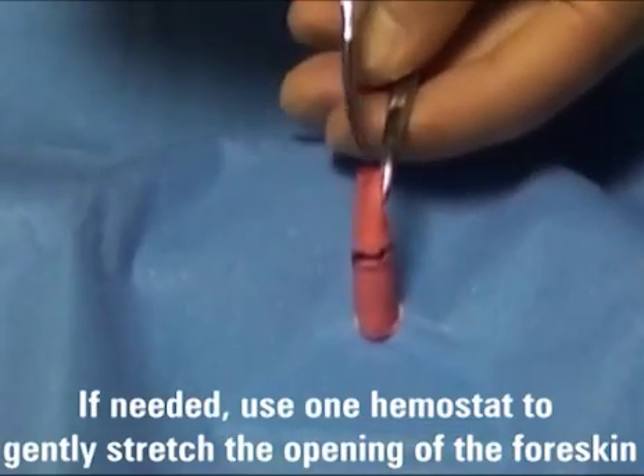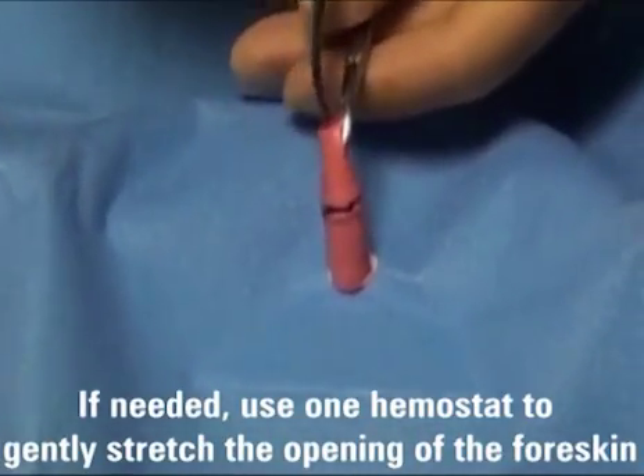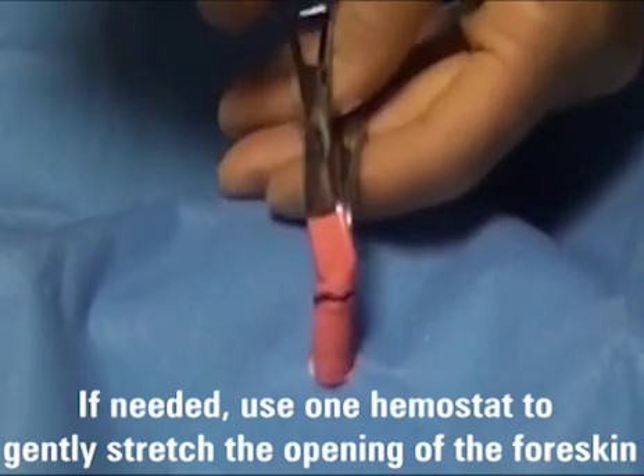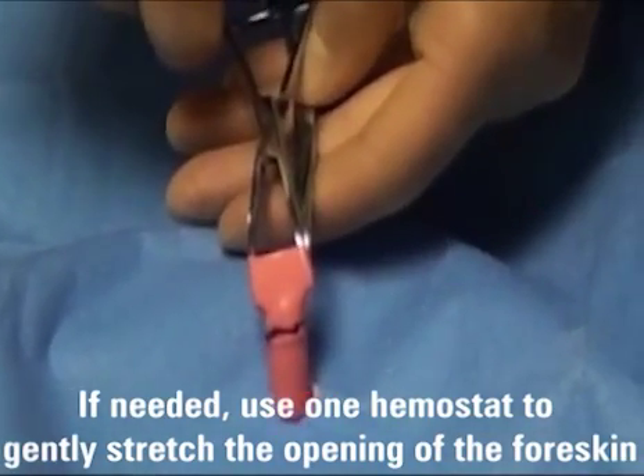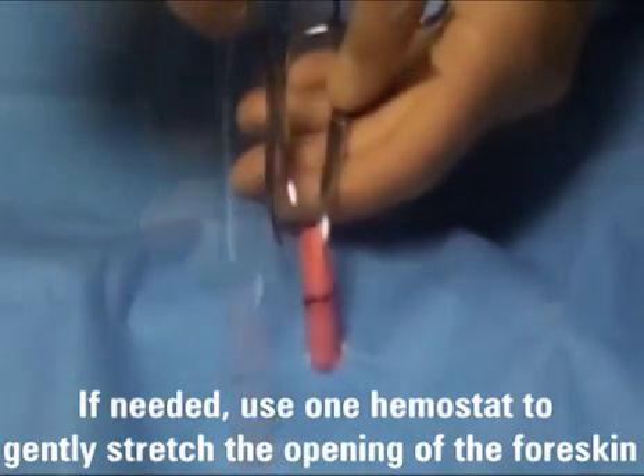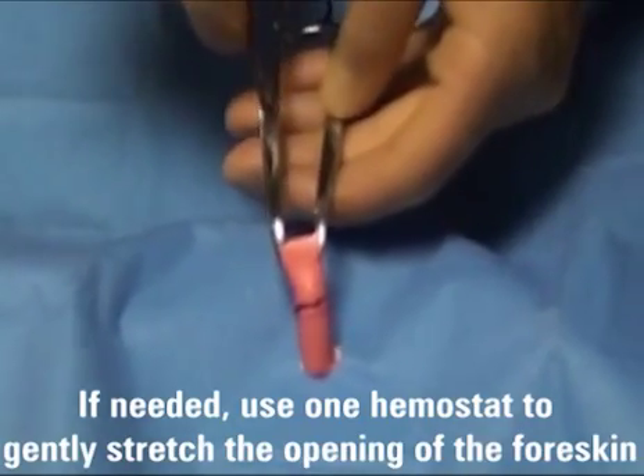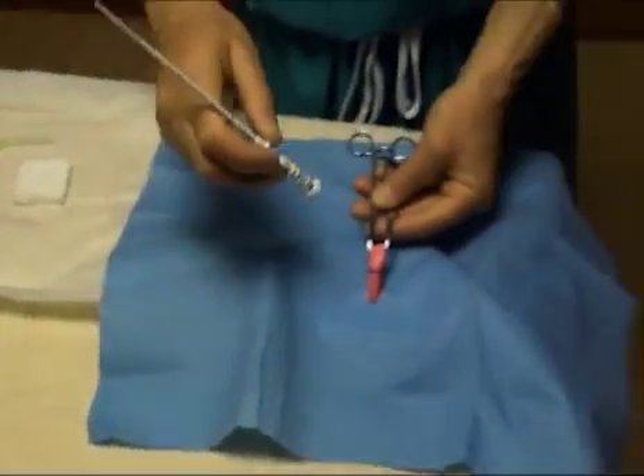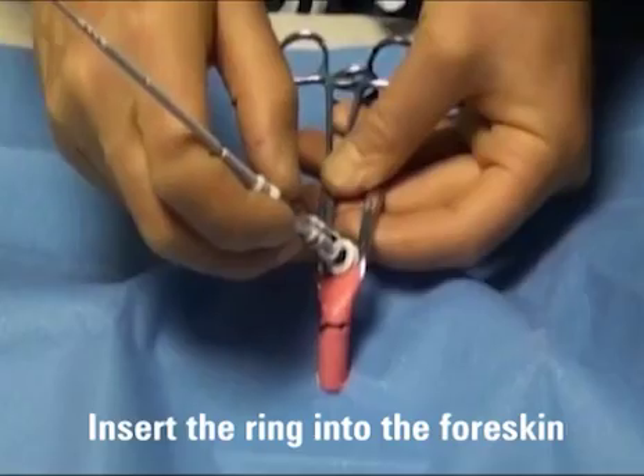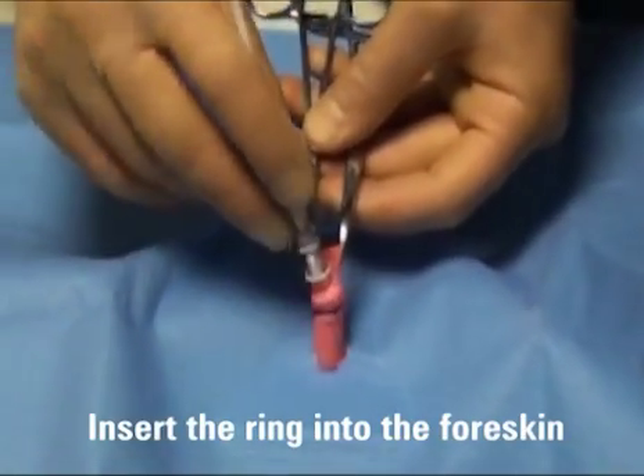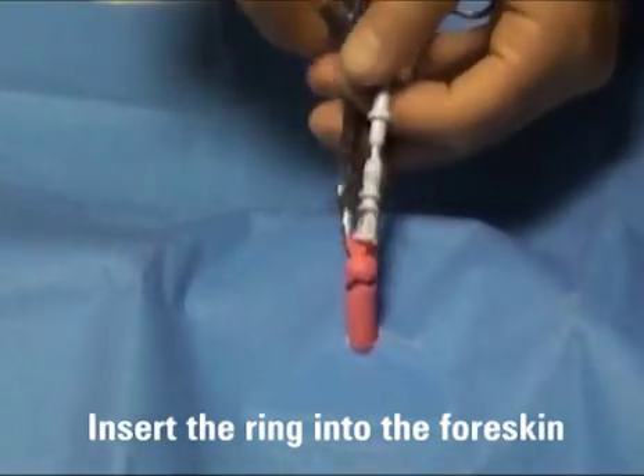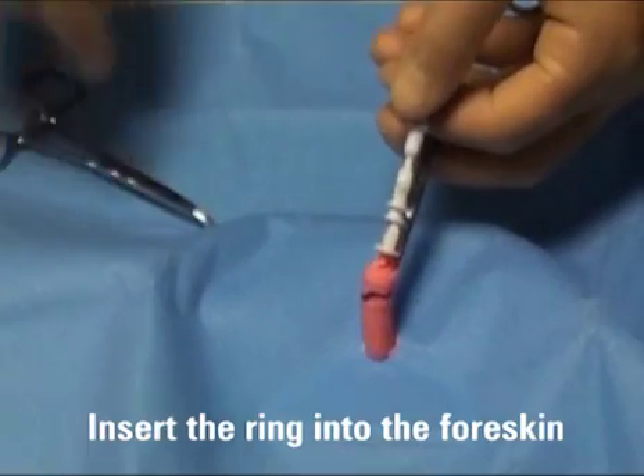If needed, detach one hemostat and use it to gently stretch the opening of the foreskin to make sure the opening is large enough to accept the shielding ring. Reattach the hemostat in the same position as before. Holding the probe like a pencil, apply a small amount of lubricant to the shielding ring and insert the ring into the foreskin that is being held open by the hemostats.